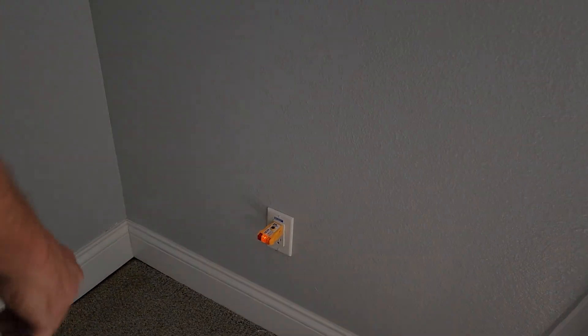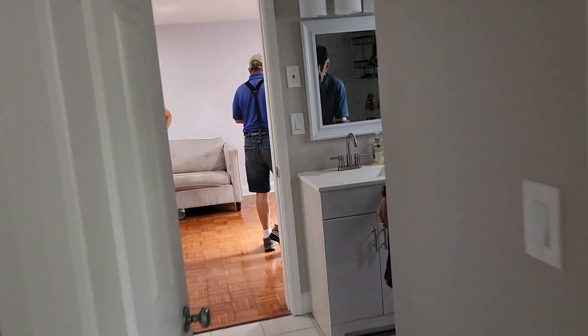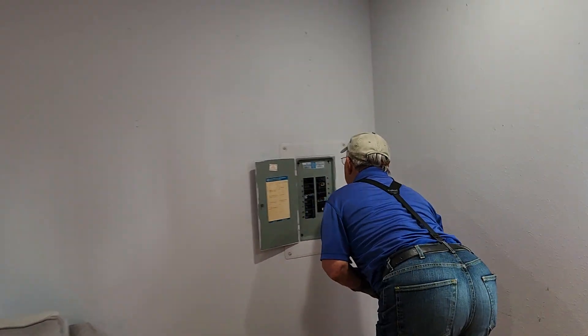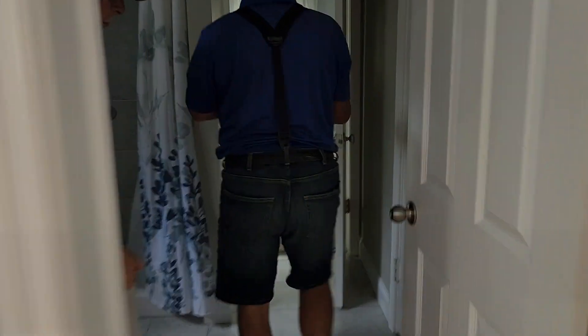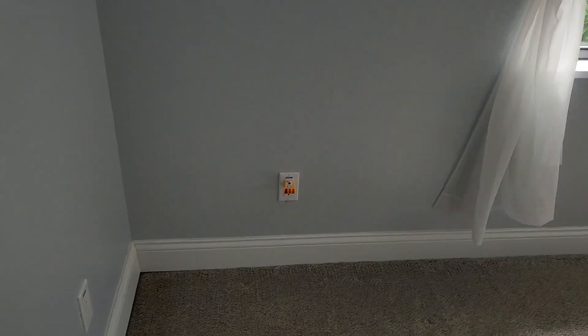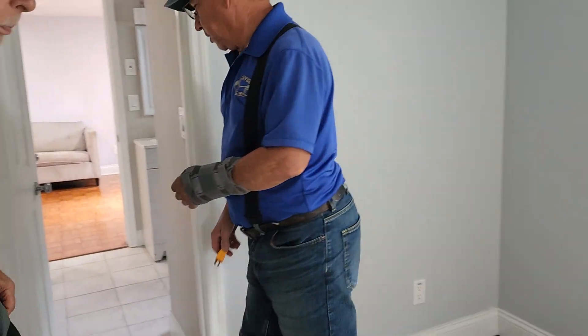That won't open the circuit. When you use the test function here, that's going to open this circuit. And now it's off. See, because this device is looking for something that's not there. But you can't fool the circuit breaker.